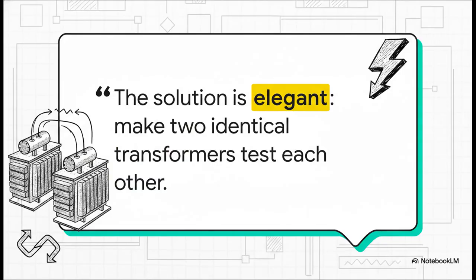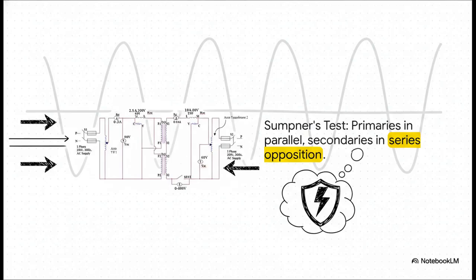It's called Sumpner's test, although you might also hear it called the back-to-back or regenerative test. And the concept is just pure engineering elegance. Instead of testing one transformer against some giant, power-hungry load, you make two identical transformers test each other. Okay, here's the setup. You take the primary windings, the inputs, and you connect them in parallel to one power supply. Then you take the secondary windings, the outputs, and connect them in series, but you wire them to oppose each other.